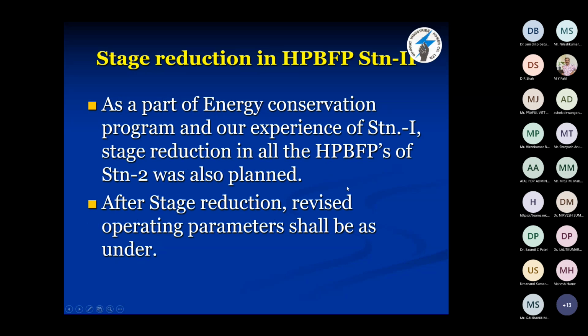Now, the same type of exercise was carried out in station 2. Earlier I said what station 1 and station 2 are. Station 1 is 145 megawatt and station 2 is 165 megawatt. So definitely in station 2, the pumps are also of higher capacity. So as a part of energy conservation and our experience of station 1, stage reduction in all BFPs of station 2 was also planned. After stage reduction, revised operating parameters are as under.